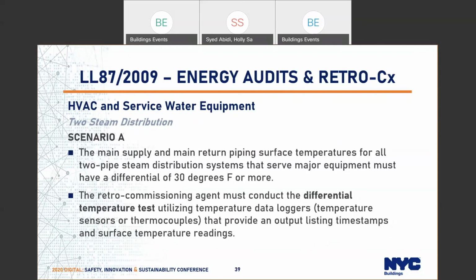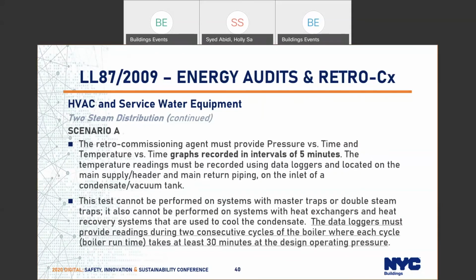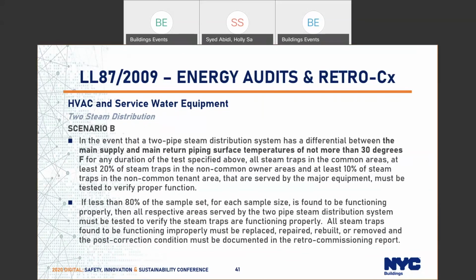However, if a 30 degrees differential cannot be proven, then the retro-commissioning agent has to demonstrate by testing steam traps that at least 20% of steam traps in the non-common owner areas and at least 10% of the steam traps in the non-common tenant areas that are served by the major equipment are properly operating and functioning.